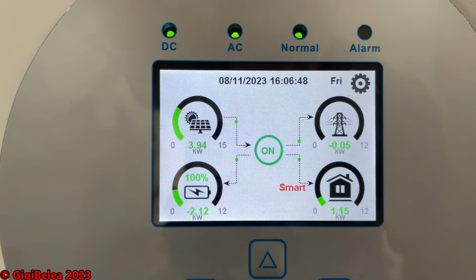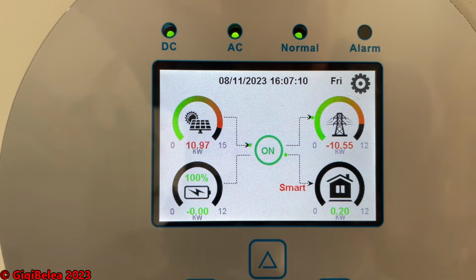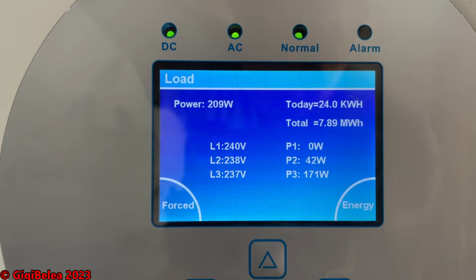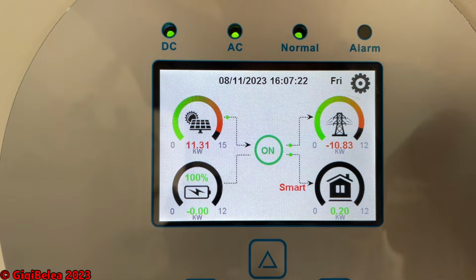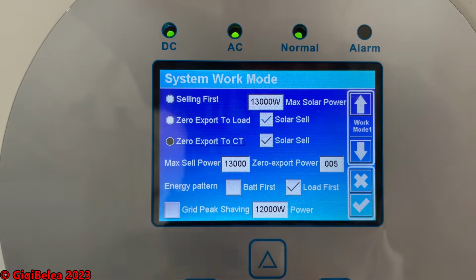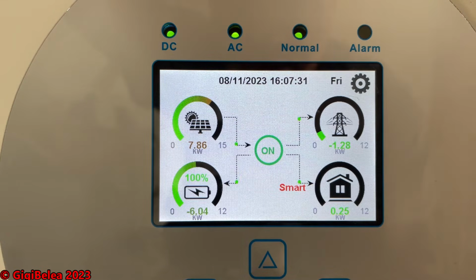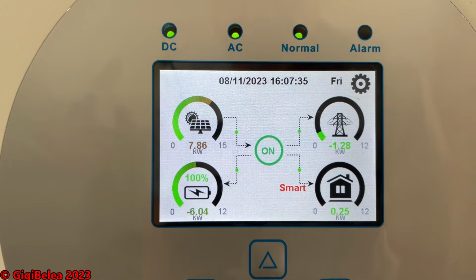If I want to cover only my load, it will cover my load and then sell everything else - the load on my load port, because this inverter has two extra ports, one of them being the load port. So it will sell everything it gets but still cover my load port, which right now has a very small load, 205 watts. I'll go back and select zero export to CT, because I need to cover all the consumption in my house, not only the load port. As we can see, the house gets 1.1 kilowatt and the rest is sold to the grid.